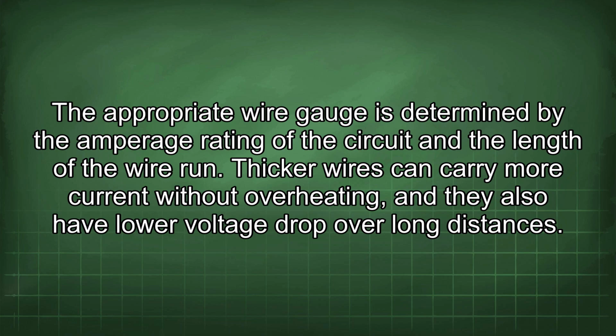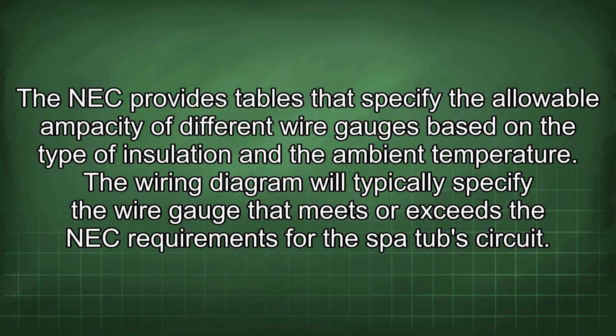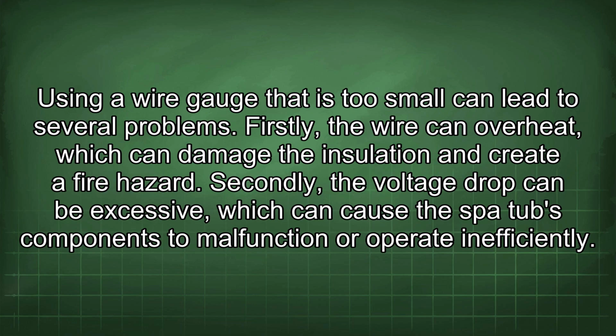Thicker wires can carry more current without overheating, and they also have lower voltage drop over long distances. The NEC provides tables that specify the allowable ampacity of different wire gauges based on the type of insulation and the ambient temperature. The wiring diagram will typically specify the wire gauge that meets or exceeds the NEC requirements for the spa tub's circuit. Using a wire gauge that is too small can lead to several problems.